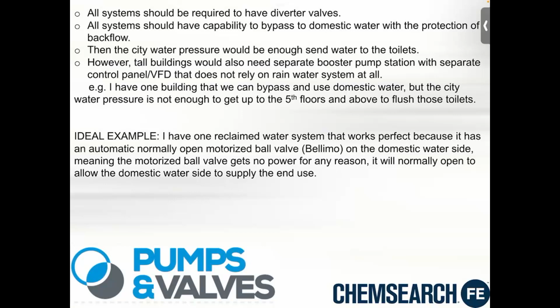For some locations, the issue is the programming. And what I mean by that is, I'm just going to use examples. One of my buildings has no need for a second booster. It literally has a separate booster system with a separate control panel. It's just that the programming prevents the booster pump from running if the system is shut off or down for any reason, because the booster pump does not know what level the day tank is, so it won't run. It basically relies on the communication from the program to tell it to run.